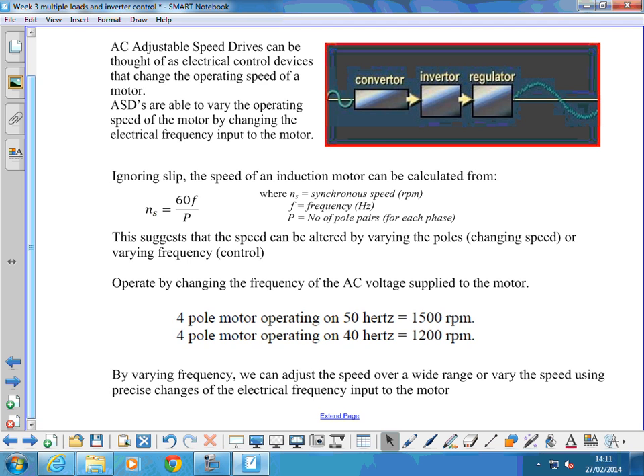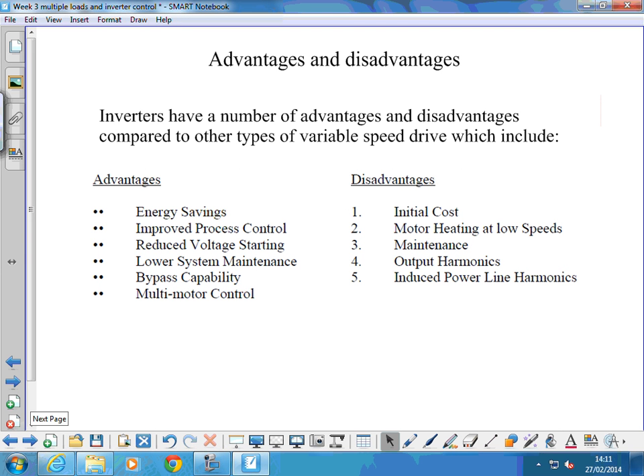So those inverters are flexible enough to be able to do that. Now, there are a number of advantages and disadvantages of inverters compared to other types of speed drive. So we've got some advantages. There are energy savings to be had by using inverters. They improve process control.